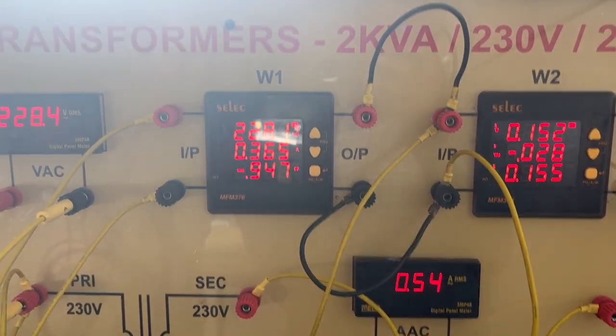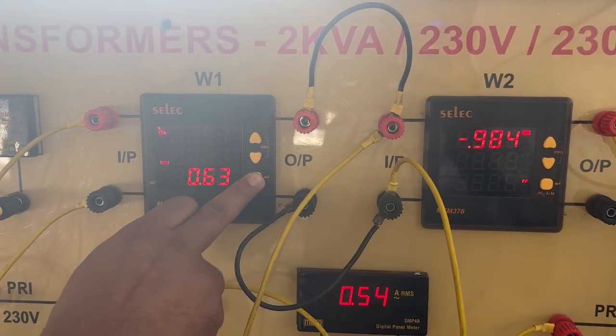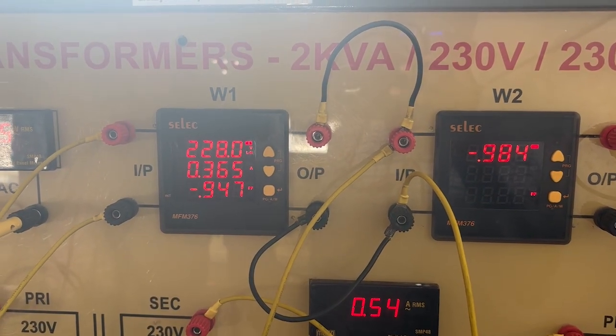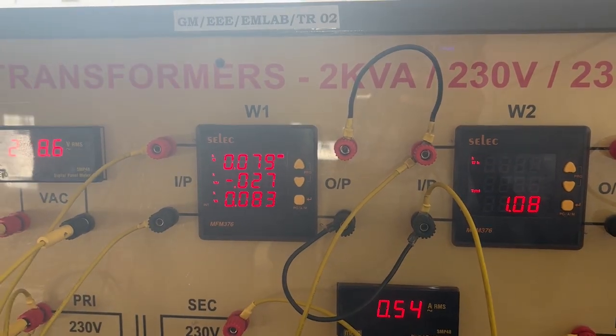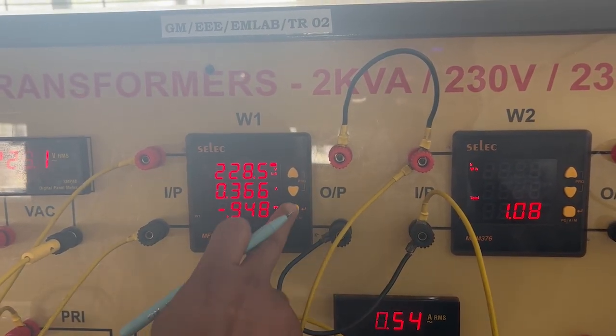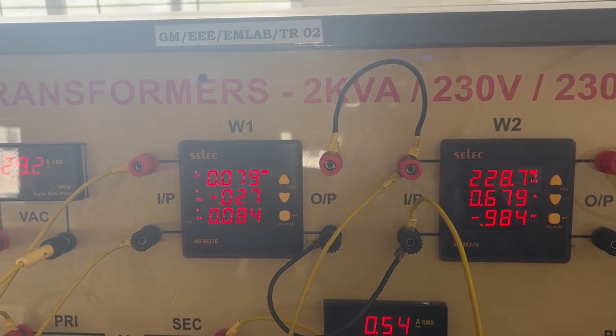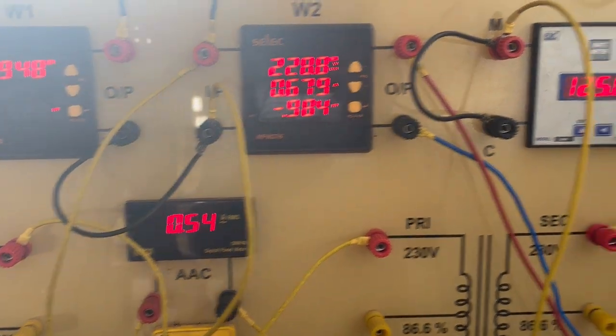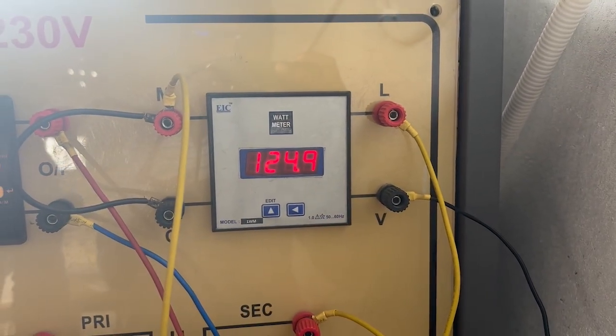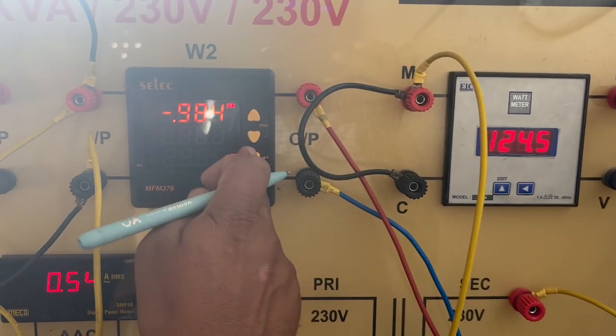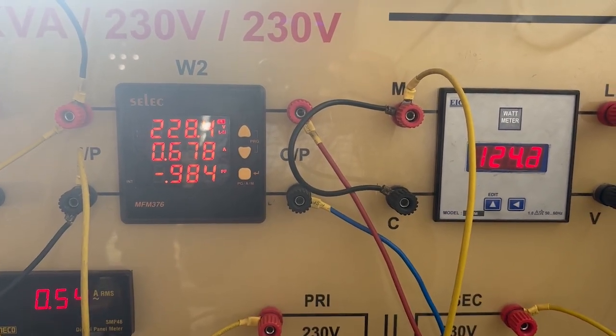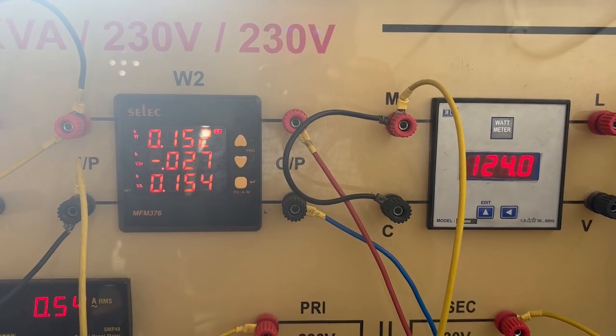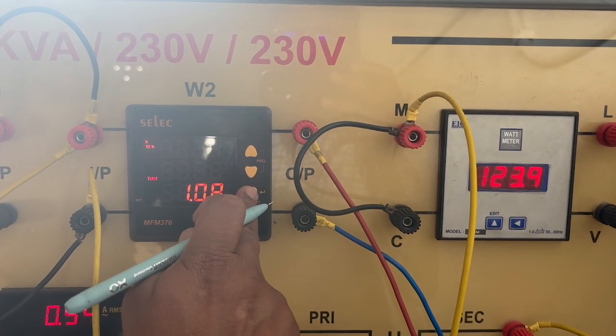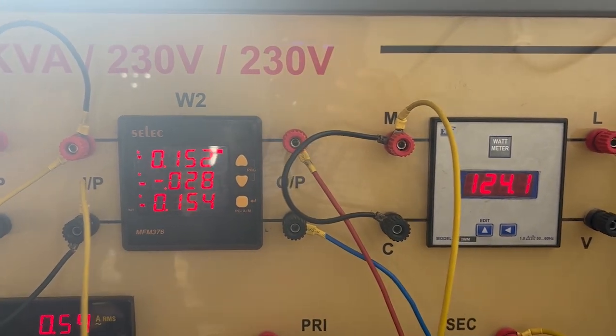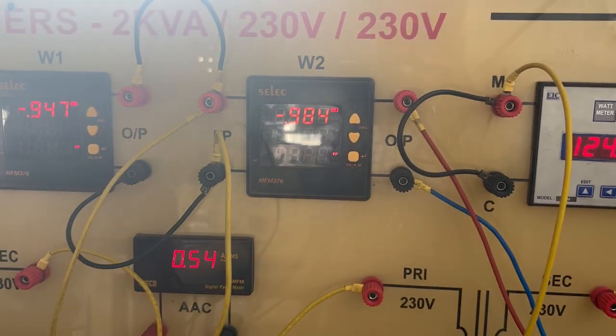Now you have to take the load readings. After applying the loads, we have to take the readings. Now V1 is 228 and the current is 0.365. W1 is 0.079. This is I2, 0.54, and W2 is 124.9. V3 is 228, I3 is 0.6 and W3 is 0.152. Again you have to take one more reading by applying the load.